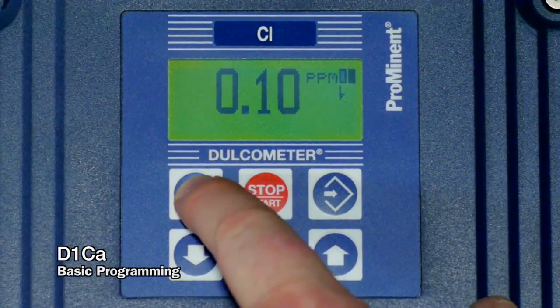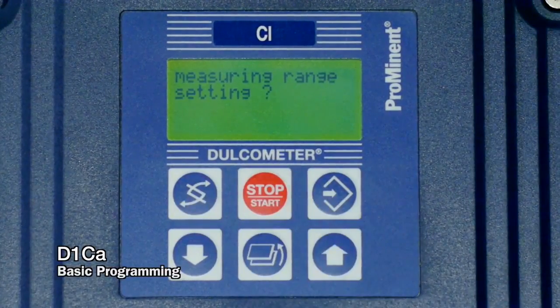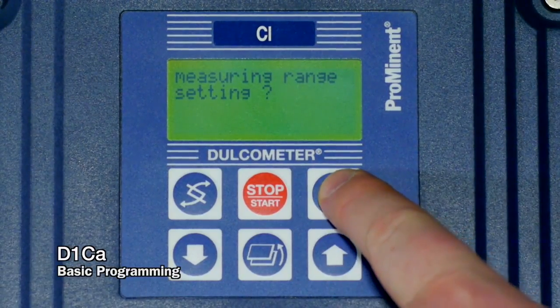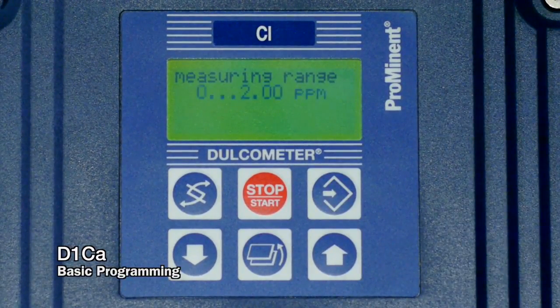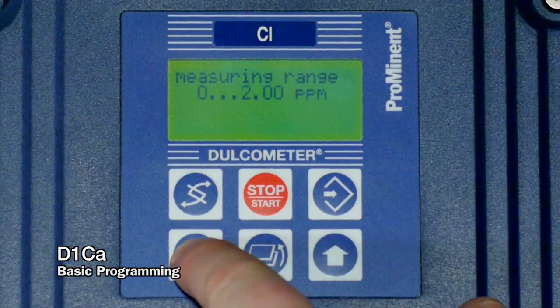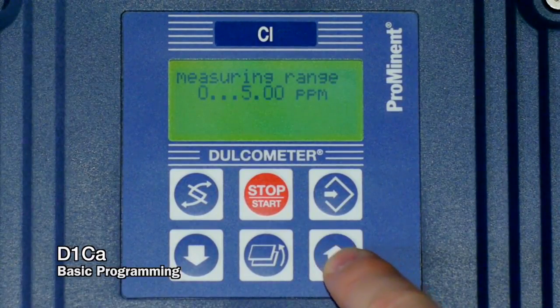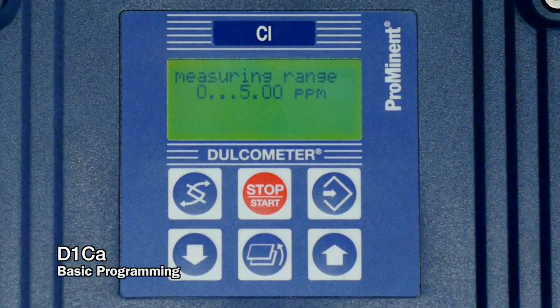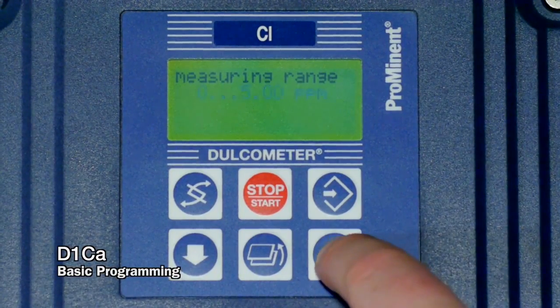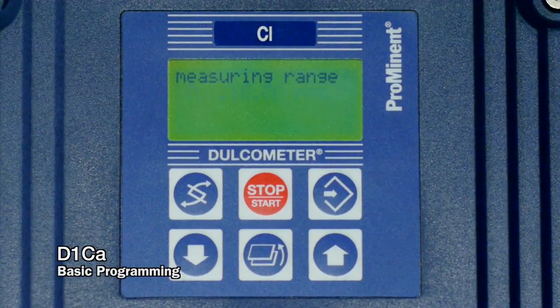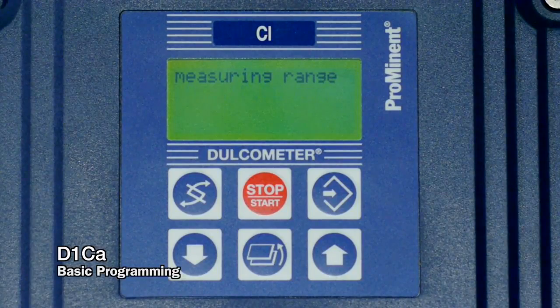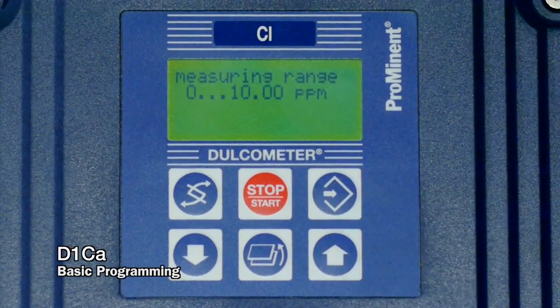Now we'll hit the change key until we see measuring range setting. Once we're at measuring range setting, to enter that menu, we press the enter button. You'll see that it's flashing the default range of the D1C, which is 0 to 2 ppm. We can change that again, whatever's flashing, with the up or down arrow button. We want to press one of those buttons until that matches what the sensor is that's hooked up to the unit. Here we have a 5 ppm sensor, or it could be a 10 ppm sensor that might be hooked to the unit. We'll leave it at 10 ppm. We'll press the enter button to accept that.